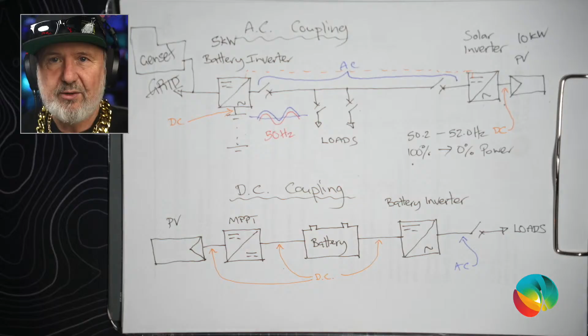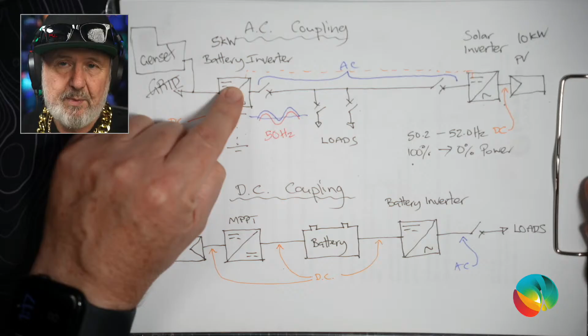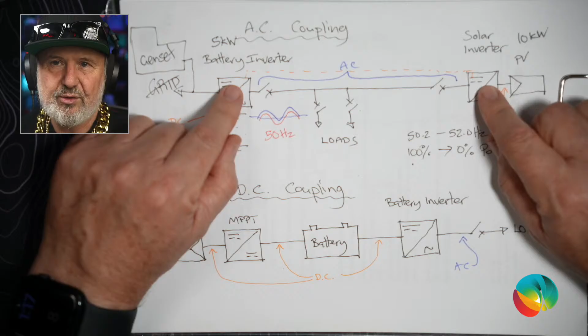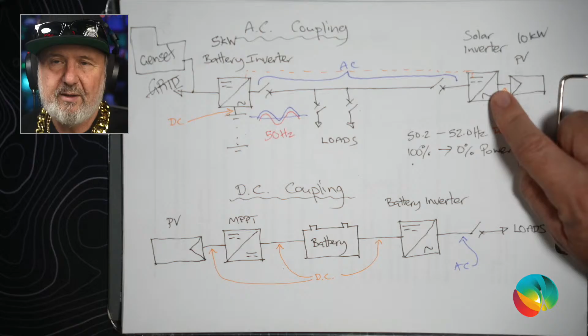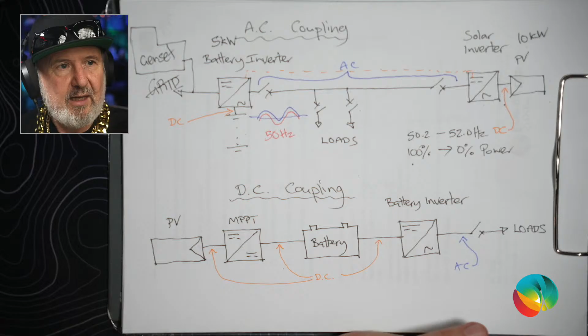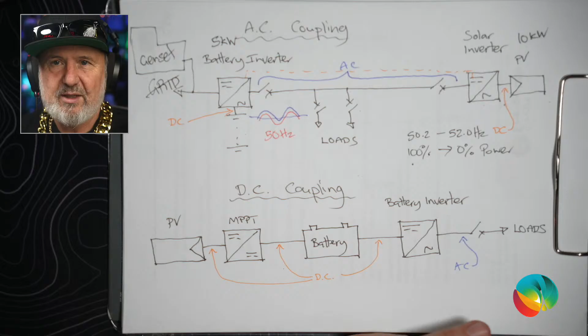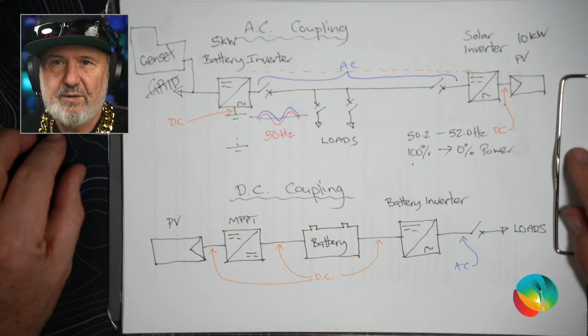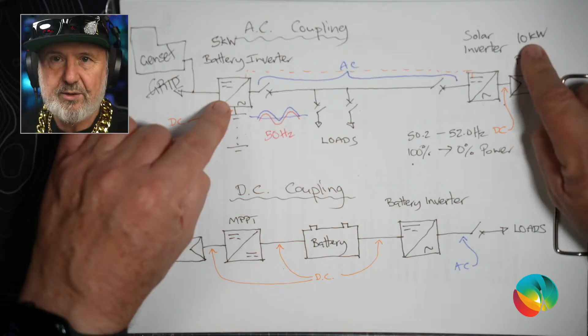So to use some brand names here, this could be a Selectronic SP Pro, and this could be a Fronius solar inverter, but it would need to be what they call Selectronic certified, because they basically program the comms to suit the way that Selectronic want to control the solar inverter. So this would be a Selectronic certified Fronius inverter. They have done it with other brands like ABB, SolarEdge, Kaco, but those relationships have fallen away, so it's now just ABB, I believe, and Fronius. So there's an example of comms is very fast and often means that you can have a bigger ratio of solar inverter to battery inverter.